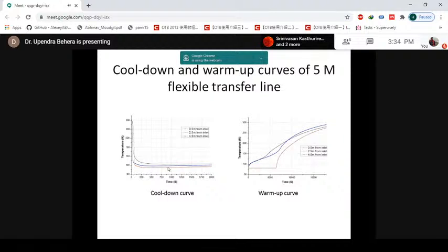So we'll test it there. But before that, this is the information which we have tested, and we checked that this bellow is working even for liquid nitrogen flow, and there is no sweating. We achieved 10^-4 millibar, but this improves to 10^-5 millibar when passing liquid nitrogen. One can see that by 200 seconds, or by 3 to 4 minutes, this total 5-meter long transfer line is getting cooled down.